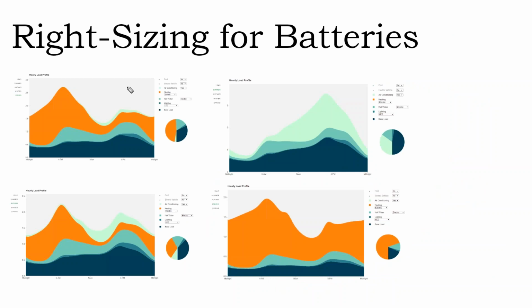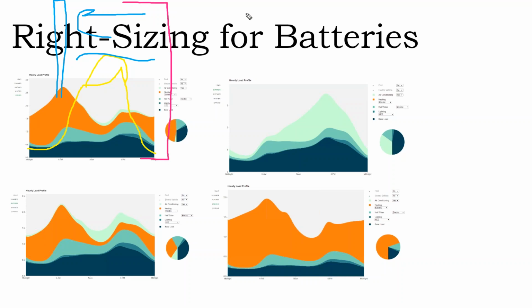So if you weren't following along on that tidbit: sometimes your solar array is going to be producing more power than your home needs, but if you zoom really far in on these graphs, the home load can be substantially greater than 10 kilowatts, the size of a standard residential solar system. So to have enough power to power the entire house when its load surges to its maximum level, it's nice to add the output capacity of the solar array along with the output capacity of the battery.